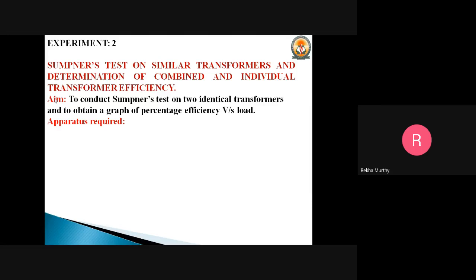that can be determined accurately, but for the determination of temperature rise, it is required that the transformer be put on full load for a number of hours. So we have to find out the temperature rise. Transformers of smaller rating can be loaded by means of lamp loads or by other means. But it is very difficult to arrange suitable loads for higher ratings of a transformer for the purpose of testing. And even if the load is arranged, it leads to a tremendous wastage of electrical energy. Therefore, SUMPNER'S experiment helps to calculate the efficiency and the regulation of the transformer.